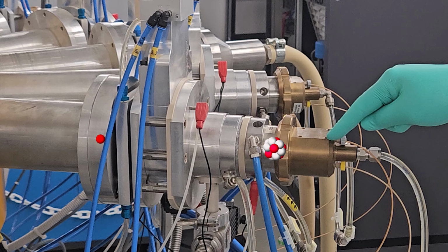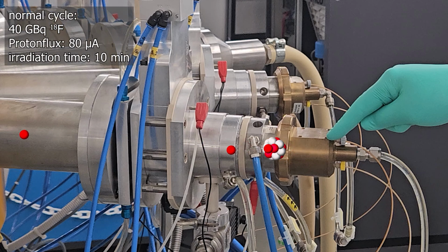Now, protons hit the oxygen 18 and via a p,n reaction produce fluorine 18. I only illustrated 1 proton, but in reality, a synthesis run can yield 40 gigabecquerels of fluorine 18 after 10 minutes at a beam current of 80 microamperes. Microamperes is a common exam pitfall. We are more familiar with amperes in the context of electron flow, but it actually refers to just the flow of charges, and it also includes the positive charge of protons or deuterons.